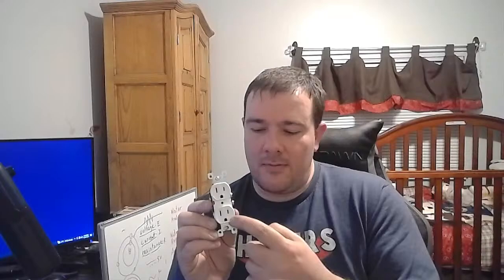In a lot of older houses, this third prong, the round one down here, does not exist because the electrical code did not require houses to be grounded. And over time, grounding became more of a commonplace thing because of safety, and it stopped a lot of fires, which is what the National Electrical Code is for. But that green screw is your ground, and should something short circuit, then it will take the current through the ground away from wherever the short circuit is. It'll pop the circuit breaker, which is another protection device, and let whoever happens to be trying to fix it fix the problem so that no fires start.